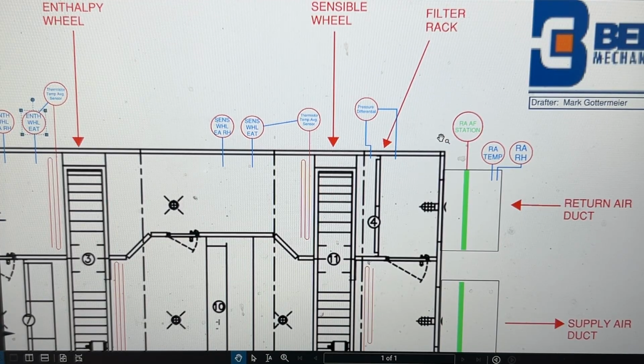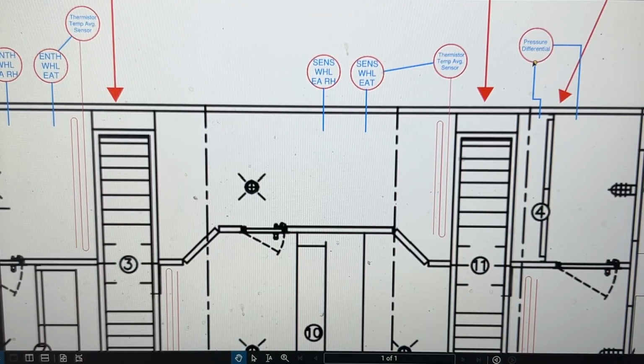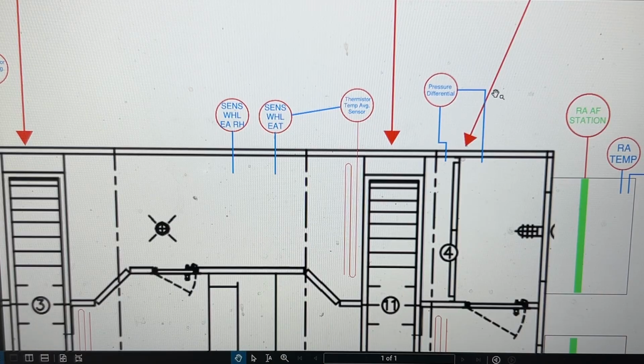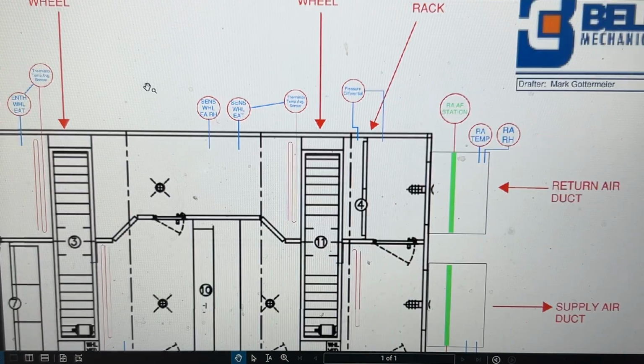All right, so our filter rack is here, which will help protect our wheel. We also have another pressure differential Magnehelic gauge on the side. So we've also got that static pressure sensor as well. So we have the visual with the Magnehelic, and we also have the controls component to that as well. We have another averaging sensor on the exhaust air side of the wheel. That gives us our exhaust air temp for the sensible wheel. We also have a relative humidity sensor within that chamber.